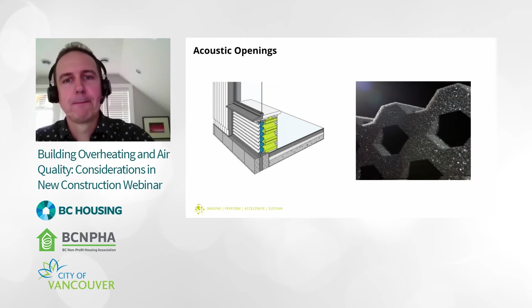A key part of this is applying engineering rigor, making sure things are fully designed to be effective. There are a number of ventilation standards, notably ASHRAE 55, adopted by the City of Vancouver Energy Modelling Guideline and also referenced by Sadia. It states temperatures cannot exceed 80% of acceptability limits for more than 200 hours during summer months, or 20 hours for more vulnerable populations. This sets an engineering challenge and design target that we need to deliver and meet.